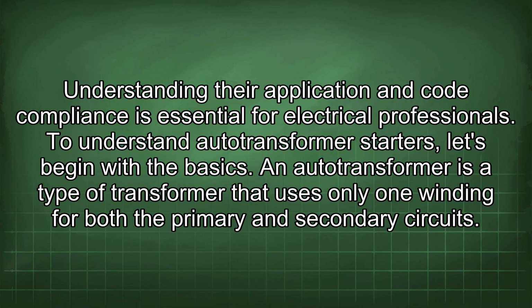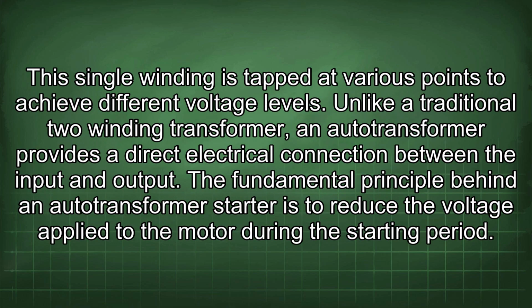To understand autotransformer starters, let's begin with the basics. An autotransformer is a type of transformer that uses only one winding for both the primary and secondary circuits. This single winding is tapped at various points to achieve different voltage levels. Unlike a traditional two-winding transformer, an autotransformer provides a direct electrical connection between the input and output.